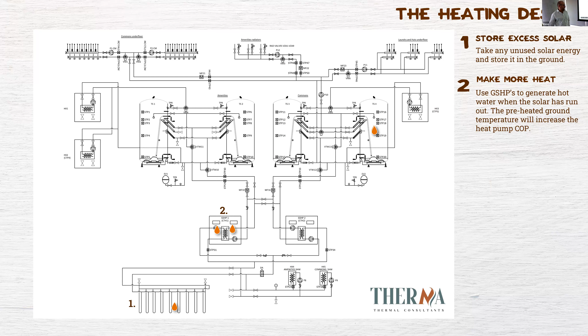The next stage is to make more heat. It's got into the evening now, temperatures have dropped quite dramatically outside, so we need to start running the underfloor heating. First thing we do is bring up all that loaded energy from the bores and get it into the heat pump, and that increases the COP of the heat pump quite dramatically. With those bores sitting at about 12 degrees down the bottom, we could be hitting COPs of 4. If we charge down there and pull that in at a much higher temperature, bringing it back up to 12, those COPs can be 5, 6. So it's a big jump, just by running a small little pump on a small little heat exchanger, a massive COP gain.